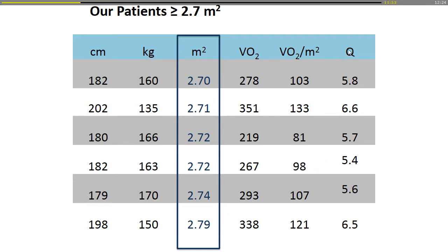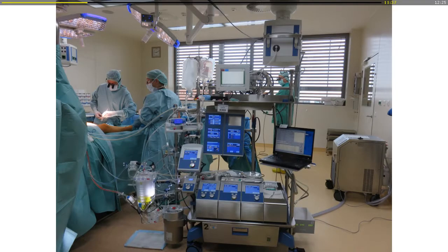When you look at the flows, the highest flow that we did run was about 6.6. If you have to look at an oxygenator according to whether I should use parallel because of flow, you're probably looking at another situation in which you probably would need an extra pump. So, that's right. This is our system. We use the S5 with an external pump here, and this way we can keep our lines relatively short.